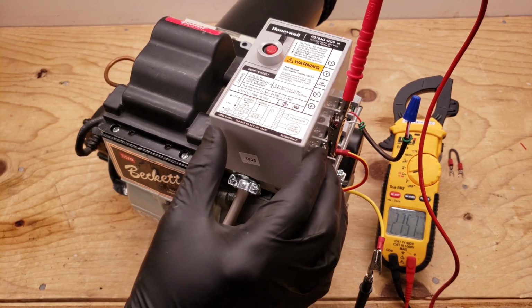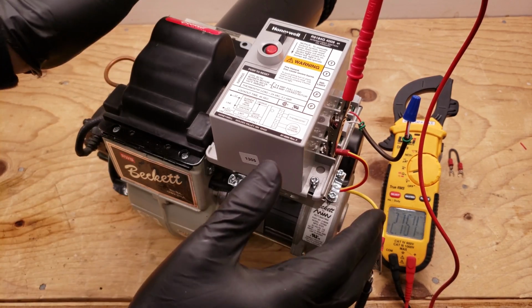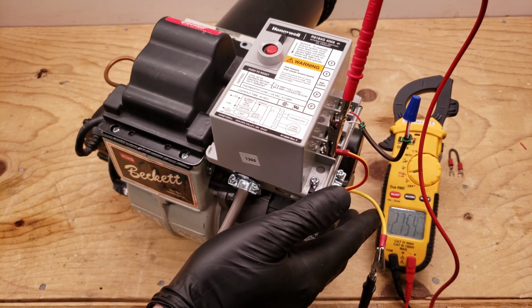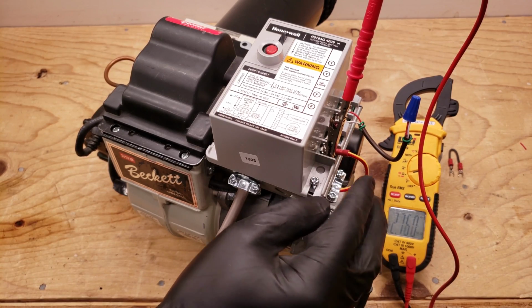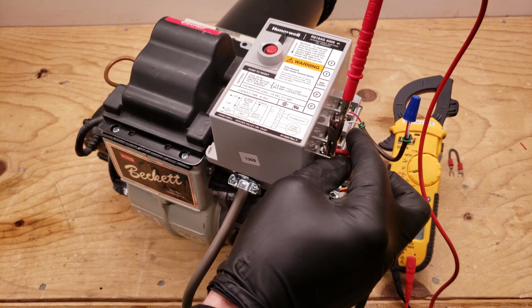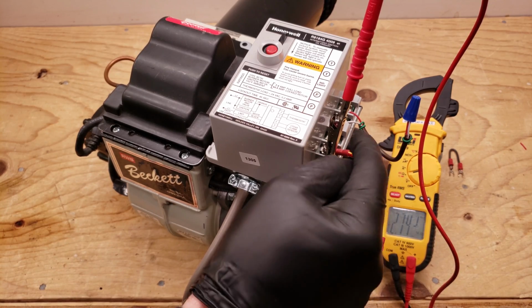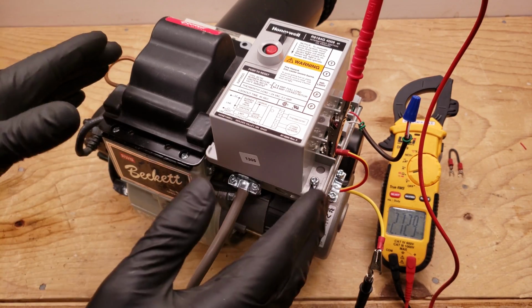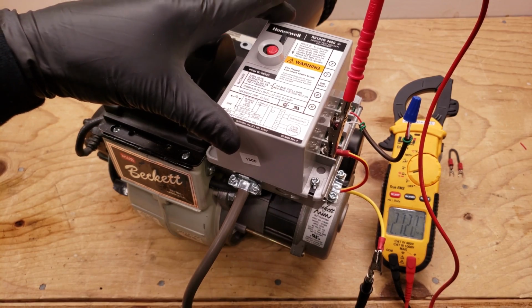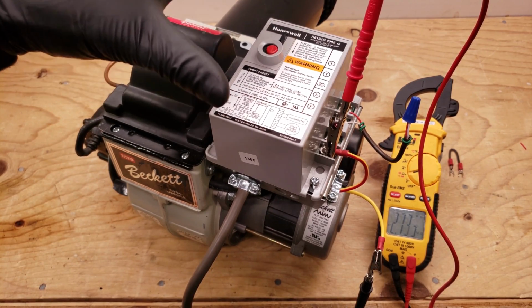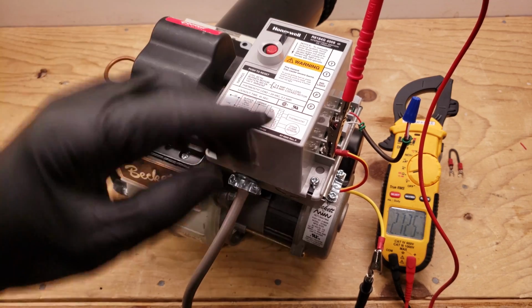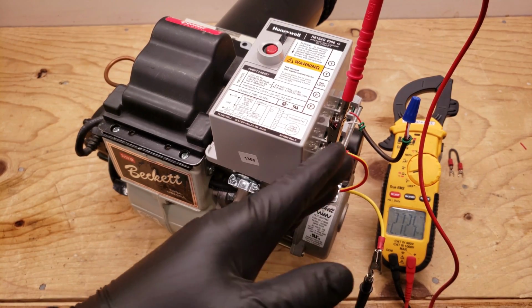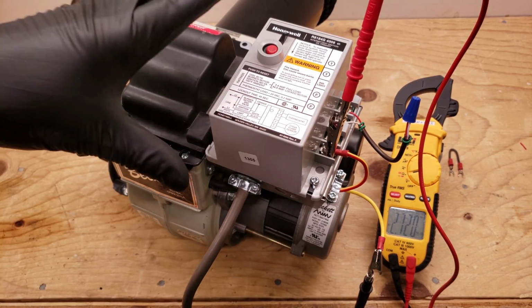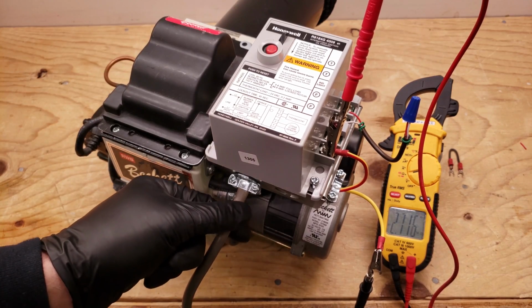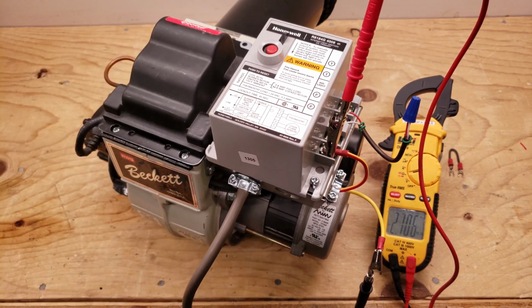And this oil primary control should be able to turn on even with this wire off, because it's such a high resistance reading, it's as if they're not touching right here. So whether this is connected or not, it's still going to turn on, but it's only going to turn on for a very short period of time, because this control wants to see the resistance value lower, below 1600 ohms. So now I'm going to go ahead and apply 120 volts as the input power to this control.